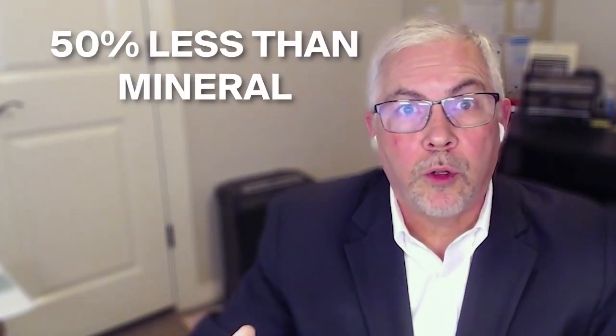There are some utilities. In fact, I visited one in Brazil recently that takes advantage of this, and they have significantly reduced the cost of designing substations by taking advantage of the high fire point of FR3 in particular, to reduce the cost of their substations. Oh, wow. The numbers that they presented to me is the cost of designing a substation today with FR3, with everything put closer together, is on the order of 50% of what it would cost with mineral oil. Wow. So if the initial cost of the liquid is a little bit higher, it's by far outweighed by the cost savings for the entire substation.